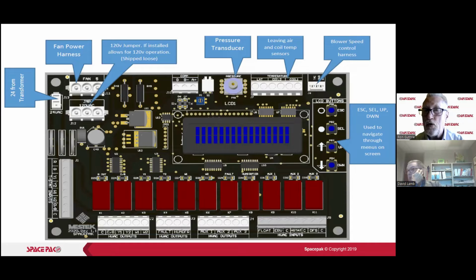Leaving air and coil temperature sensors come on the unit, but only coil 1 comes on the unit. So we have a leaving air temperature that comes on every unit. We have coil 1 that comes on every unit. Coil 1 is the DX coil, or in the case of the hydronic model, it's the chilled water coil. All right, coil 2 we add if we're using a hot water hydronic coil.